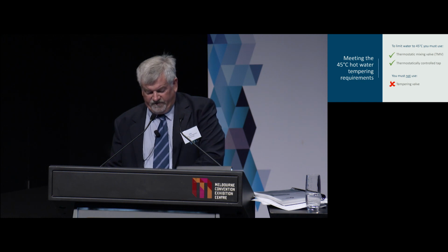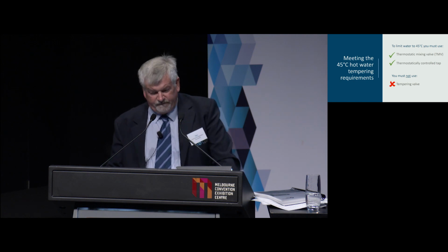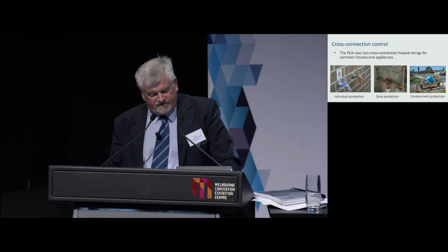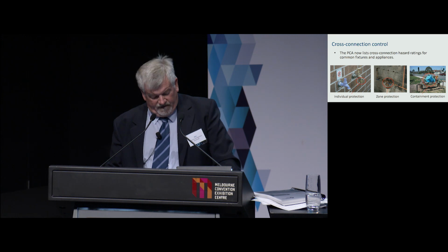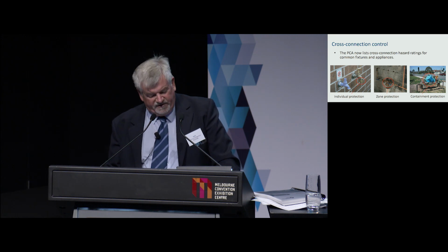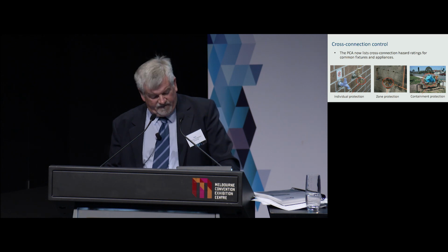Now, I'd like to run through some new requirements that have come into play for cross-connection control in Victoria. Cross-connection hazard ratings for common fixtures and appliances are now also listed within the Plumbing Code of Australia. These hazard ratings must be used when you select your backflow prevention device for your installations.